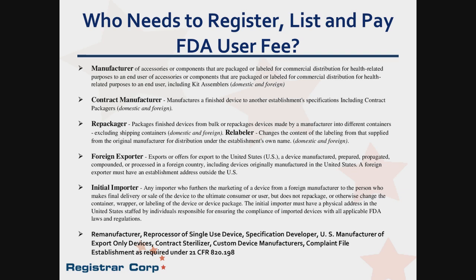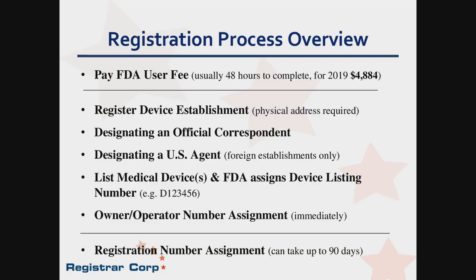Reprocessor of single-use devices, specification developer, or even US manufacturer of export-only devices, contract sterilizers. All these functions require FDA registration and listing. On that slide is a quick overview of the process. If you have never had an FDA registration, or you're just thinking of starting here in the US, that is the flow chart for how to start. The first thing is you have to pay the FDA user fee for 2019, beginning in nearly 2 weeks, October 1st. The fee will be $4,884.